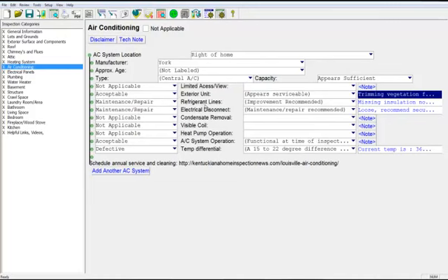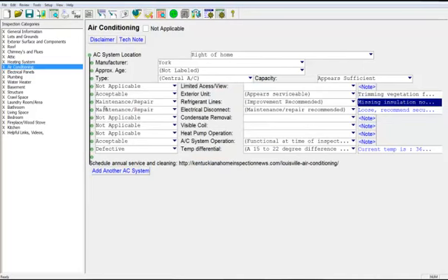The next line is for the refrigerant lines. In this case it's maintenance repair because we are missing insulation, and we're recommending installing insulation where we're missing for the proper function. So you can see where we've done maintenance repair and then improvement recommended and then noted the concern.